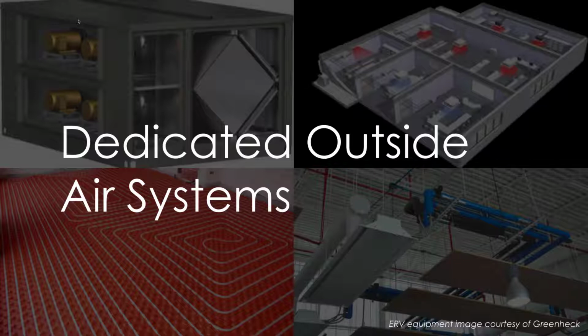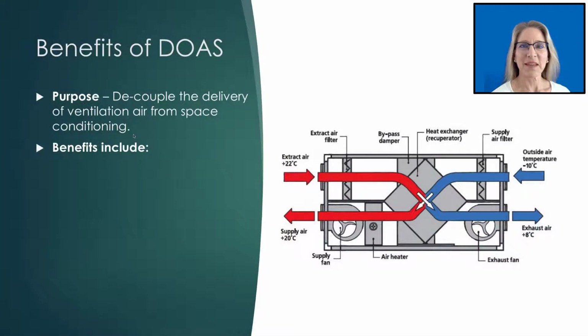So now, let's move on to dedicated outside air systems. This provision was introduced in the 2015 WSEC. The purpose of this requirement is to decouple the delivery of ventilation air from space conditioning. Traditional HVAC systems are sized for peak heating or cooling conditions. When there is no call for space conditioning, this system has to operate often outside its optimal range to continue to provide the necessary ventilation air for the building occupants.